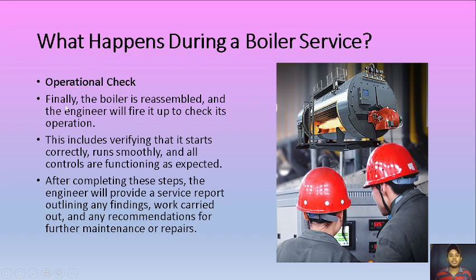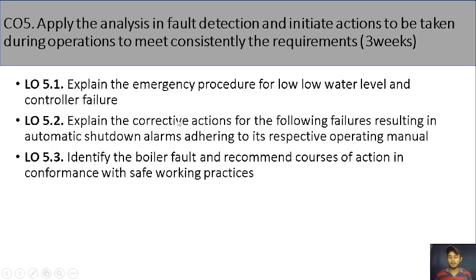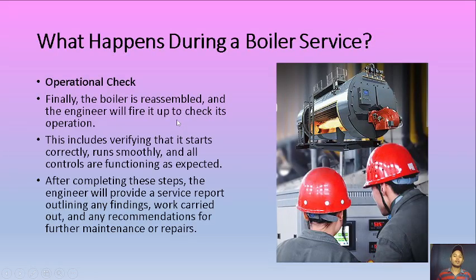Next, operational check. Finally, the boiler is reassembled and the engineer will fire it up to check its operation. This includes verifying that it starts correctly, runs smoothly, and all controls are functioning as expected. All the temperature and pressure readings are okay. After completing these steps, the engineer will provide a service report outlining any findings, work carried out, and any recommendations for further maintenance or repairs of the equipment. Okay, so that's how we do our boiler service. That's how we ensure that the boiler is running smoothly while operating.